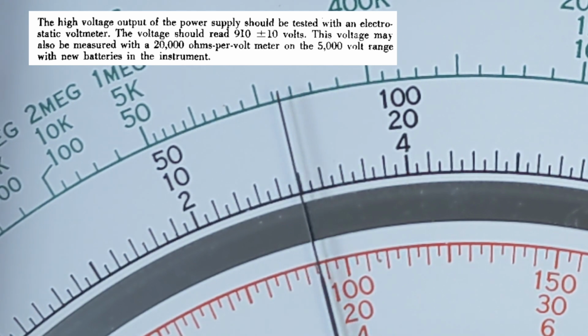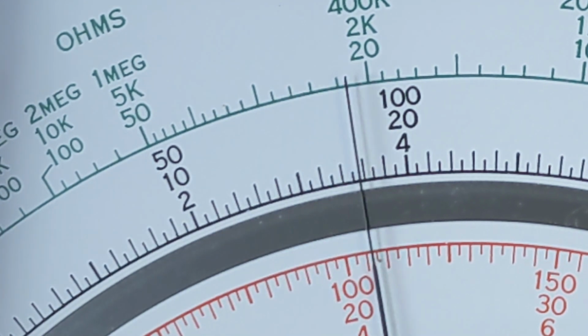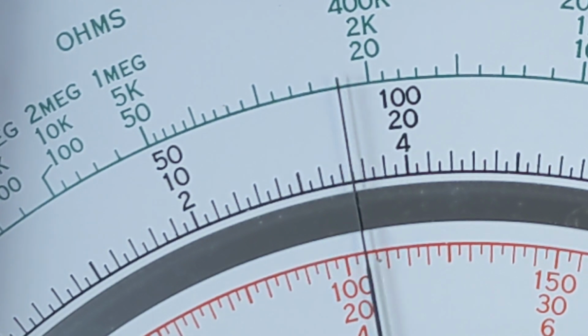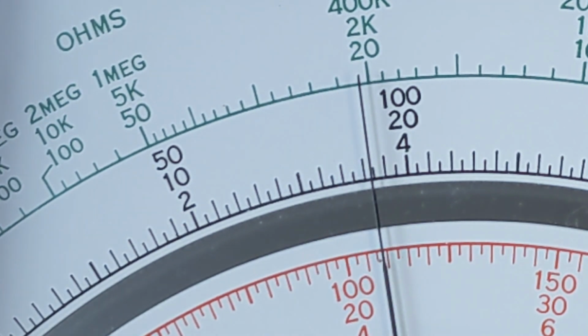So as I just turn the adjustment pot here, you can see we never really go over about 920-ish. So we're right where we want to be. And that right there is around 920 volts. So that's within tolerance. That Zener stack I'm using is 3 270 volts and 1 100 volt for a total of 910 volts. But that's a 6% tolerance. So at least with the accuracy of this old meter, which hasn't been calibrated and I don't even know, that's probably as good as I'm going to get with the tools I have available.